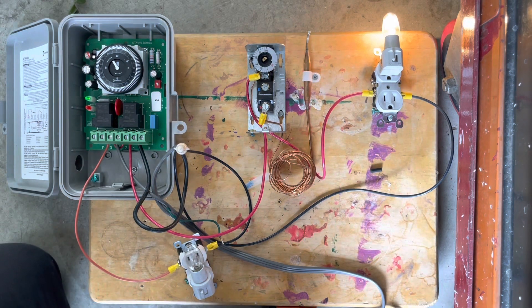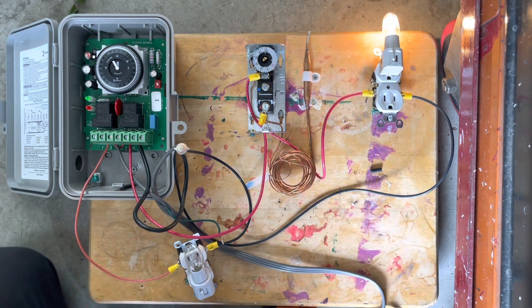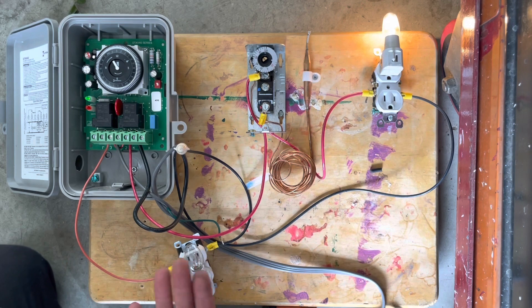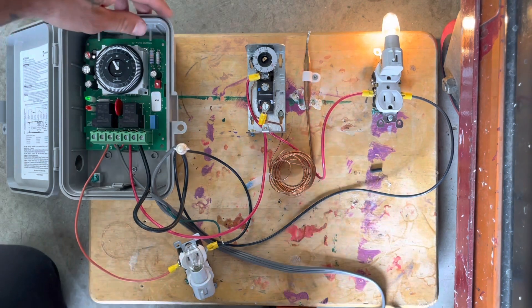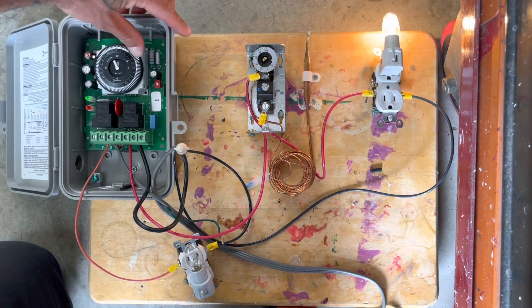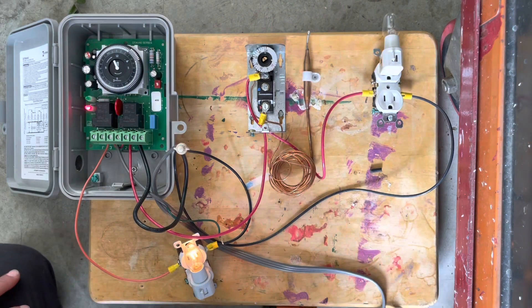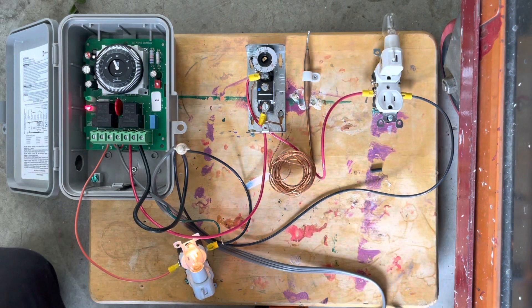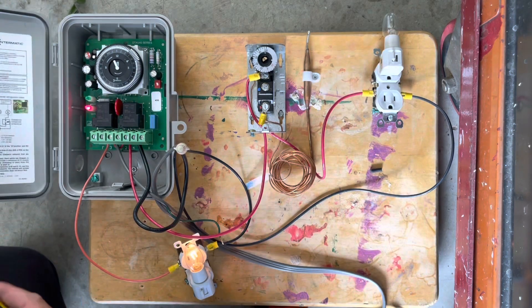There you go, simple as that. You think you're missing the X? Well, I'll show you what the X is doing. Let's say it's in defrost, defrost heater's on. Got a jumper wire here.